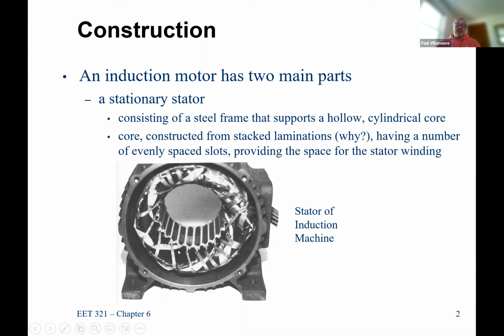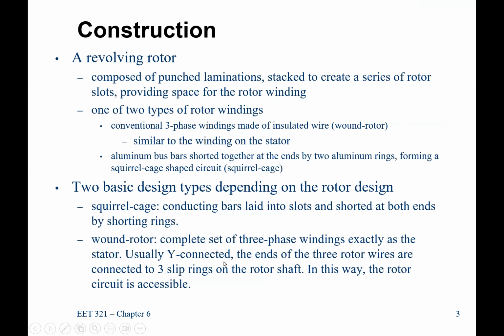So you can see the stator here. This actually shows some of the slots. And this right here, the string, just holds the winding in place. So you have a stationary stator. This is obviously hollowed out for a rotor. You have a nice circular item. We have stacked laminations because we want to limit our eddy current losses. And we always have an even number of slots, and it always has to be divisible by 3, because in a 3-phase machine, every time we add a pair of poles, we have to add a 3-phase set of windings. So if we were able to go through here, we could count the number of slots, and it would be divisible by 3.